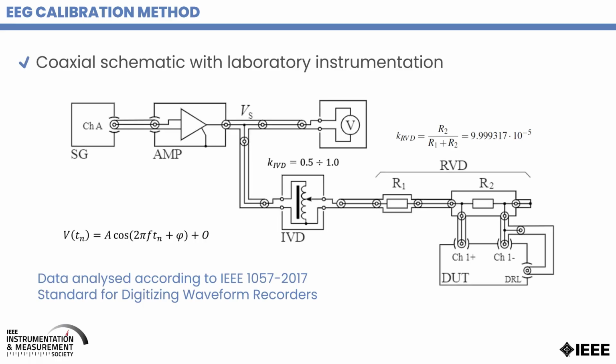We were wondering in our studies as metrologists if this was also due to some nonlinear and other kinds of effects of the instrumentation. So the first thing that we did, we started analyzing the behavior of the low-cost electroencephalograph. And we started with a procedure that serves to calibrate it.